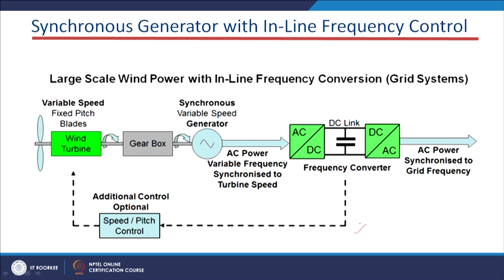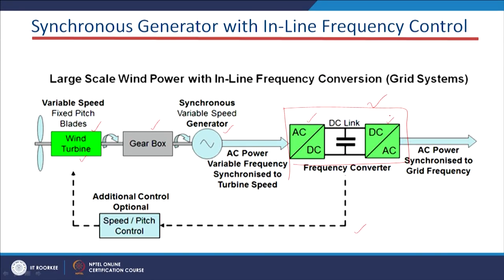This is how this variable synchronous generator-based wind system looks like. Here we have the variable speed fixed pitch blades, the wind turbine section, and the gearbox. After that we have the variable speed synchronous generator, and the extra part added here is the electronic converters. The first part is the rectifier which converts AC to DC, and the second part is the inverter which converts DC to AC power. Both converters are connected via the DC link, and the DC link voltage should be maintained at the rated values.